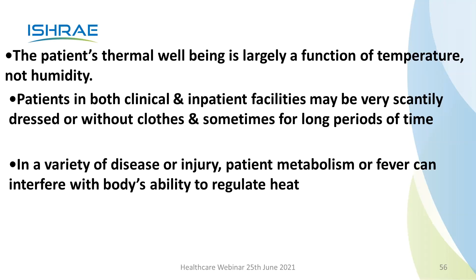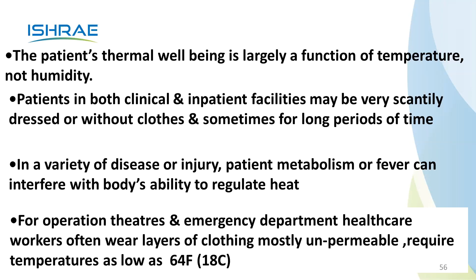So what do you do? If in that room you have got 24, 25, 26 degrees centigrade, that person won't be able to sleep. He'll be so frozen. So you should have the facility that the temperature can be raised up. In a variety of diseases or injury, patient metabolism or fever can interfere with the body's ability to regulate heat. For operation theaters and emergency department, healthcare workers often wear layers of clothing, mostly impermeable, and require temperatures as low as 18 degrees centigrade. So you've got one extreme, sometimes you need higher temperatures, sometimes very low temperatures. So be aware that the guidebooks tell you, in which area, what is the recommended temperature.